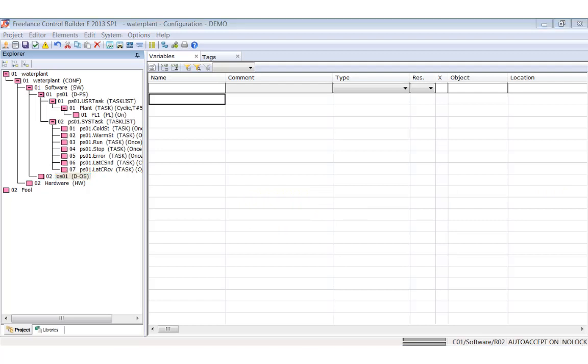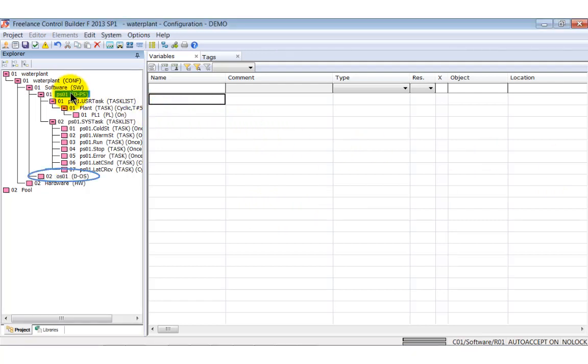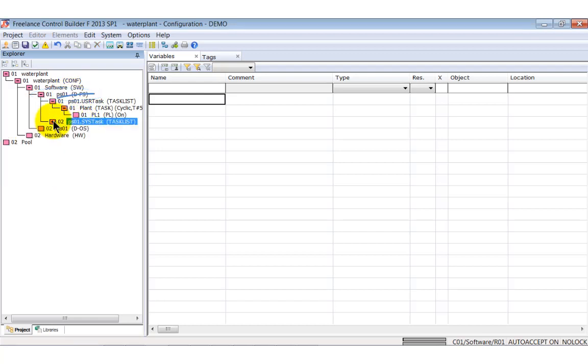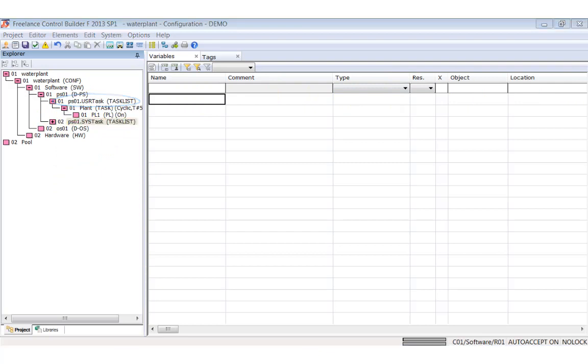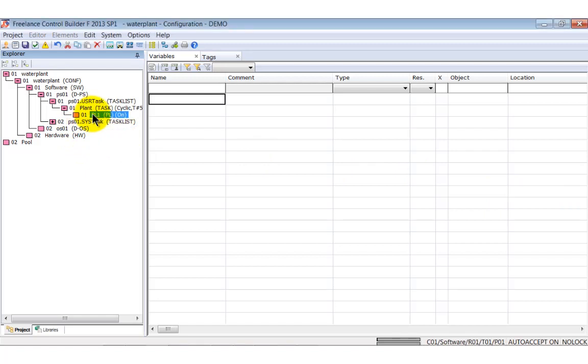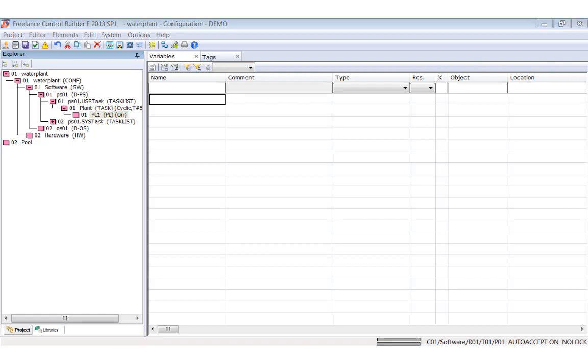With the template we have imported the following nodes: an operator station and a process station. The process station consists of one user task list and one system task list with seven system tasks. Don't worry about the system tasks for the moment. Under the user task list you see a cyclic user task with 200 milliseconds cycle time. The user task includes a program list.